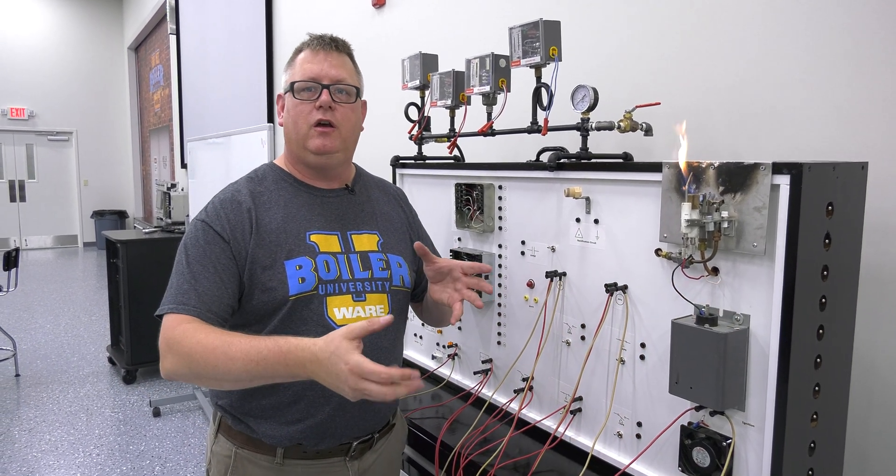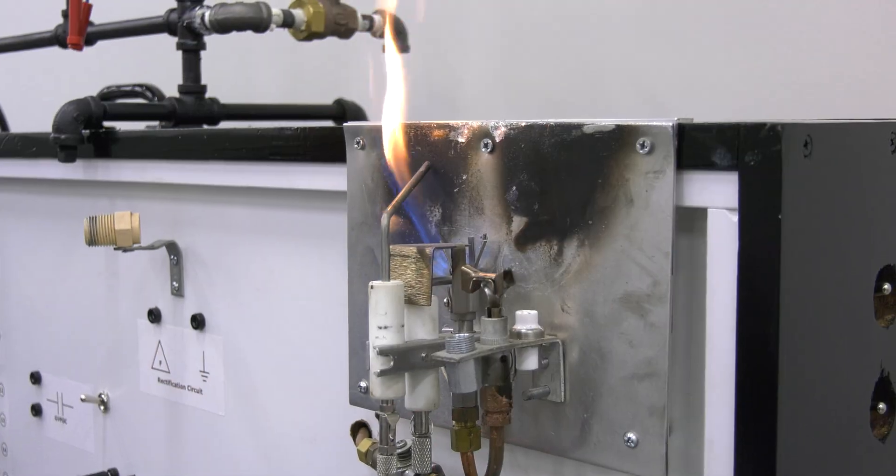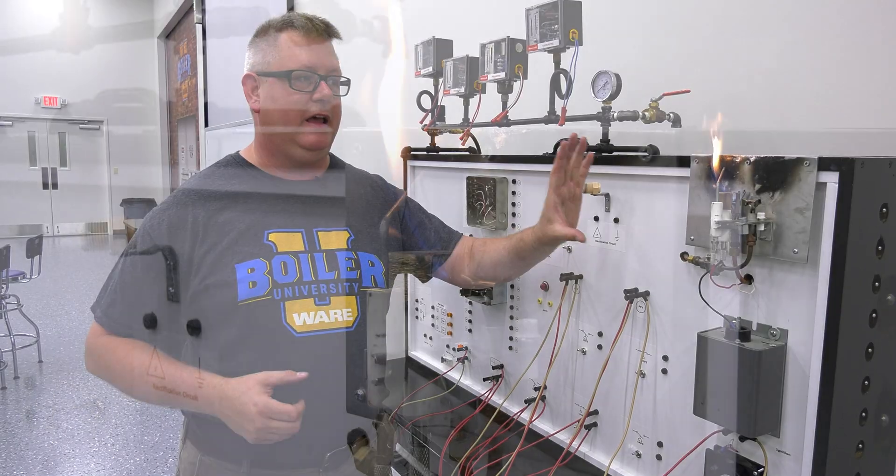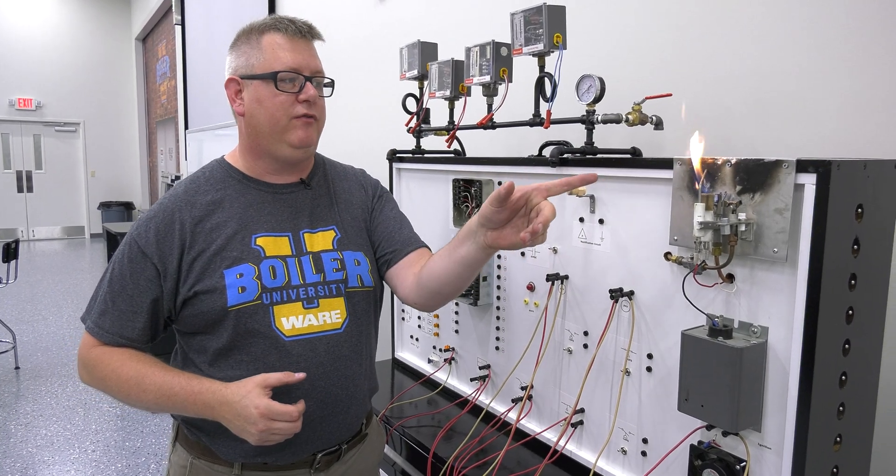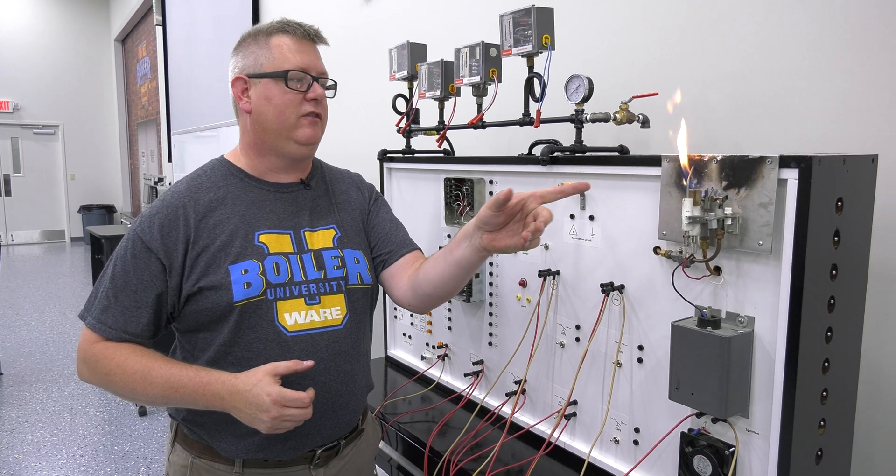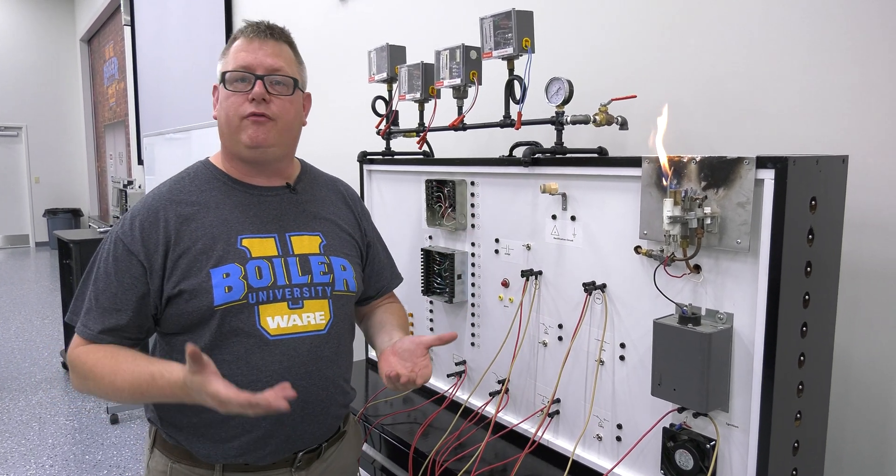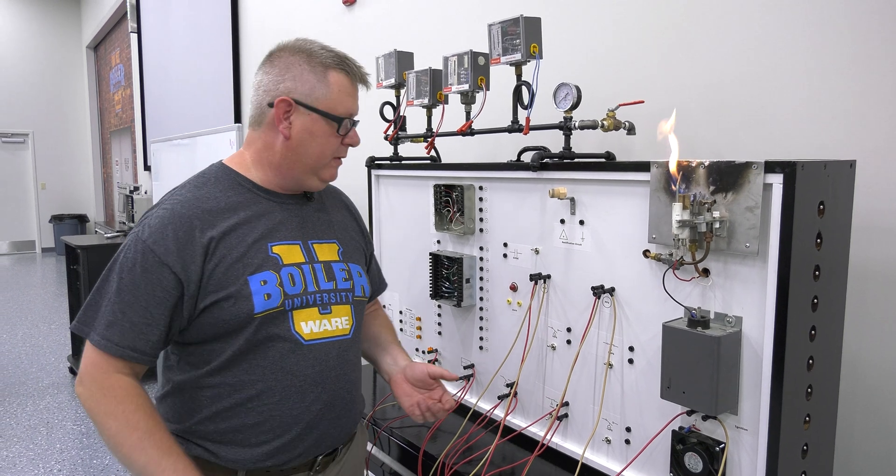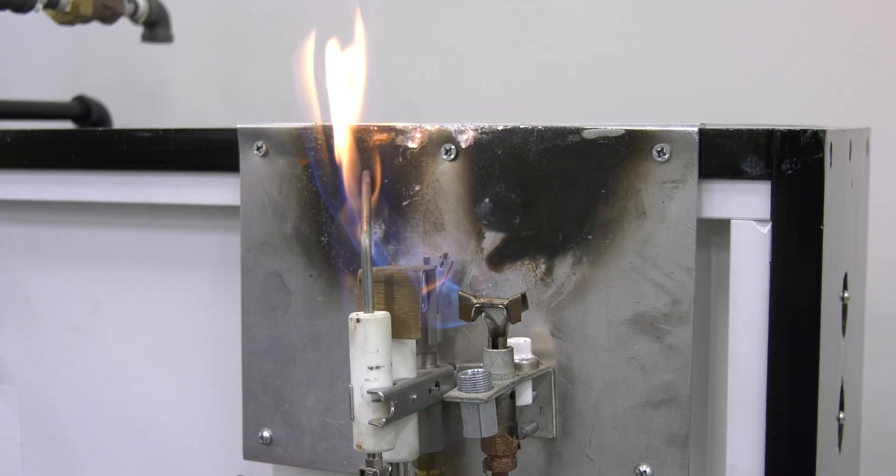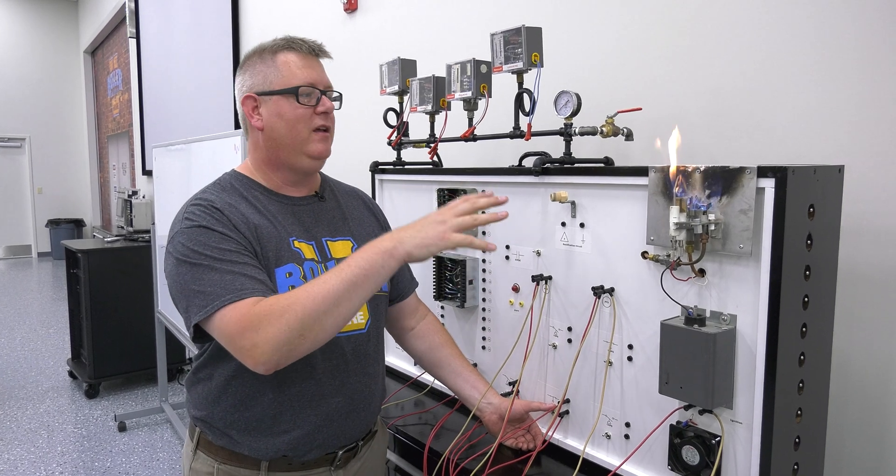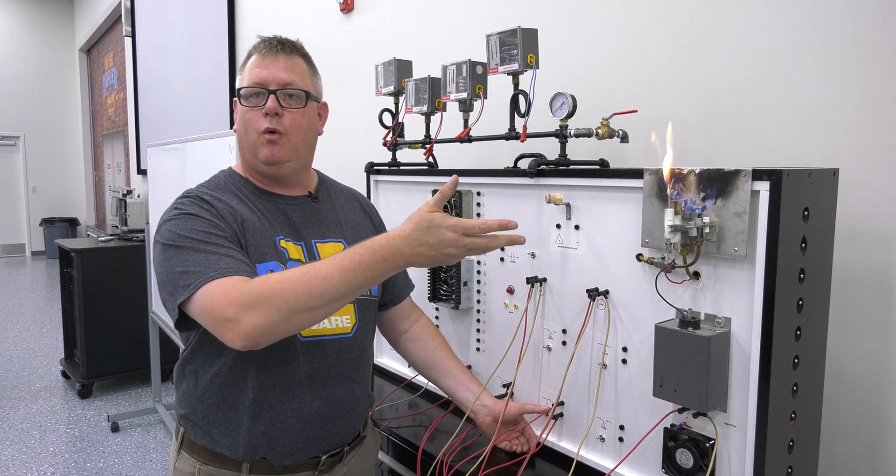With an atmospheric unit, we'll often have a standing pilot. The pilot stays lit at all times using a flame detection system to verify it's lit. When we get a call for heat, the main fuel will simply be energized—there's our main fuel, a little bit anemic there, but we get the point. When the call for heat is satisfied, the main fuel valve will shut off and the pilot will remain on.